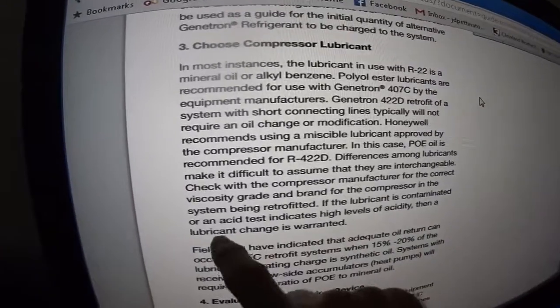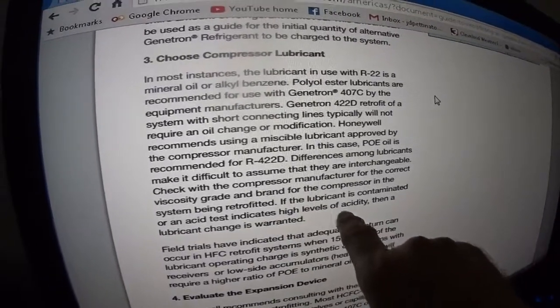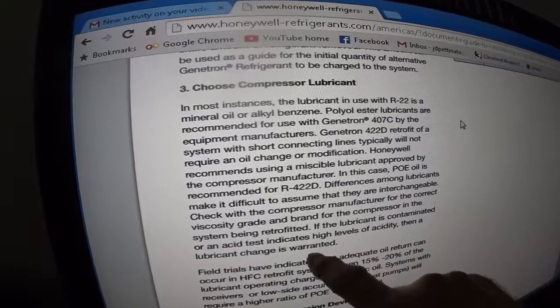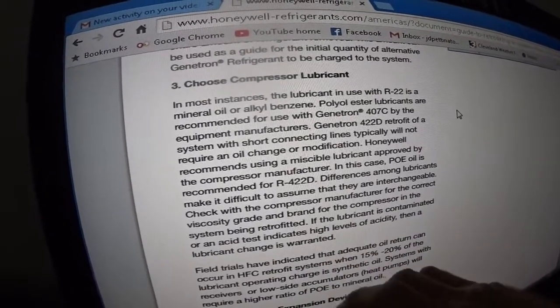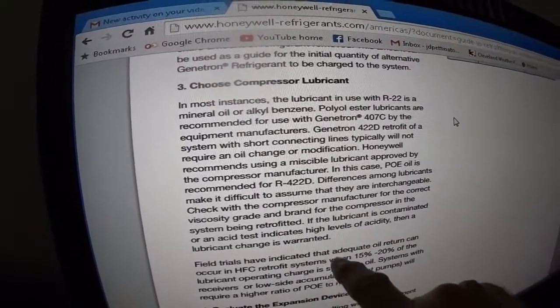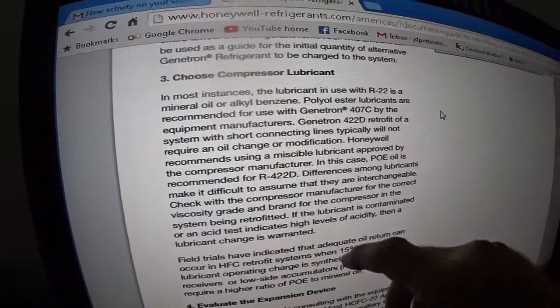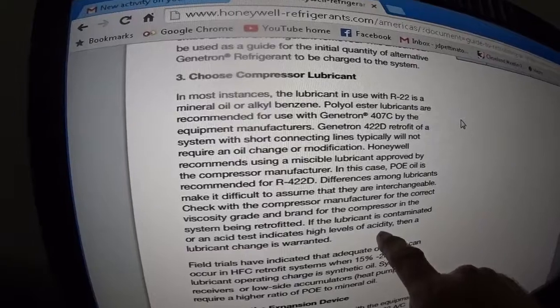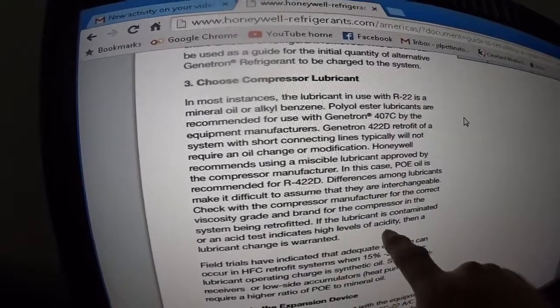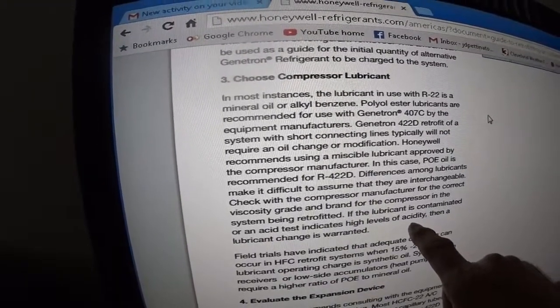If lubricant is contaminated or an acid test indicates high levels of acidity, then a lubricant change is warranted. The acid comes from the varnish on the motor windings — the insulation between the copper wires. If the motor shorts out, that varnish burns inside the compressor, throws off debris, and turns to acid. If you don't get that acid out of the system, the compressor will burn out within the year, and a new replacement compressor will also burn out within the year.